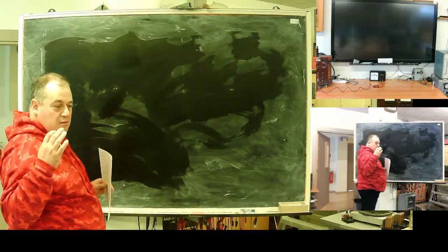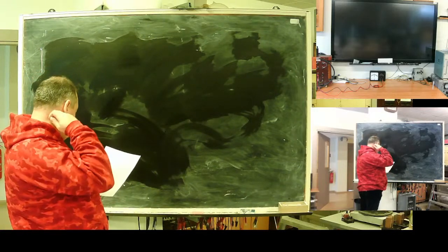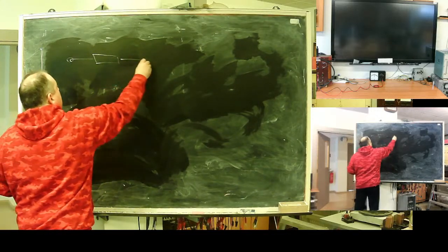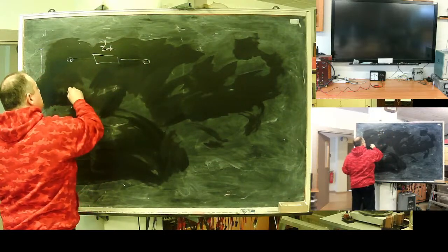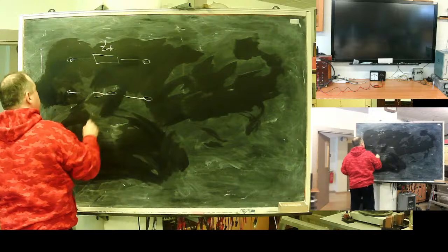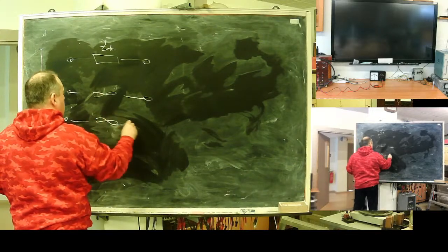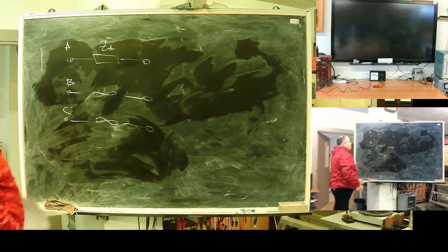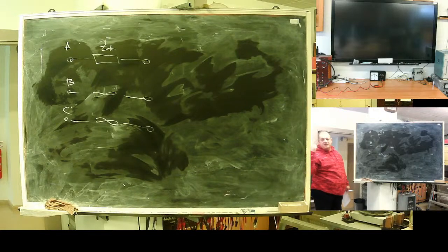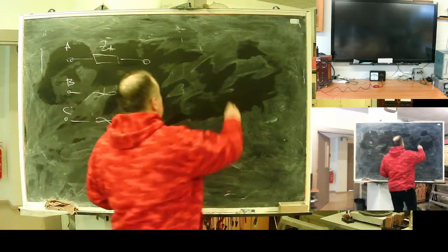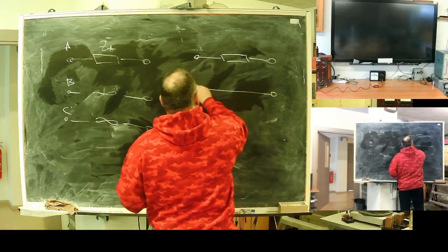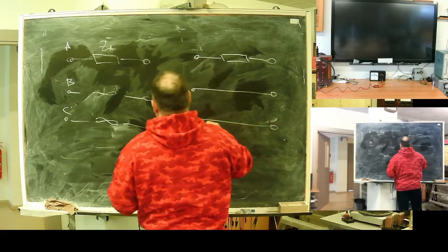For the most common purposes, two cases will work. One, when you have resistance in A phase and complete infinity in B and C. This is A, this is B, this is C. So complete infinity in B and C, only one phase is connected. That is one case. And another case, you have zero resistance in B and C.